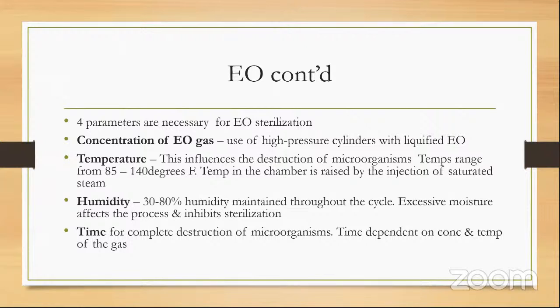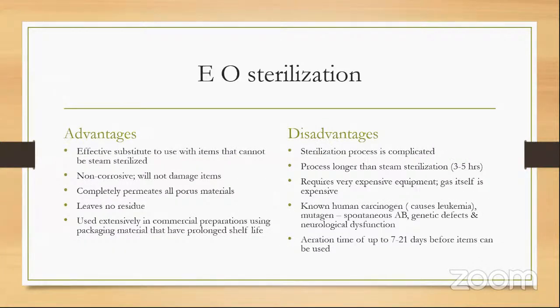So it's low temperature and there is some steam in it, because 30 to 80% humidity is needed for the efficiency of the cycle. But excessive moisture affects the process and inhibits sterilization. So it's just enough humidity, just enough heat, and just enough time for complete destruction of the microorganisms. The time for sterilization is dependent on the concentration of the gas and the temperature of the gas. But ethylene oxide sterilization can take anywhere between 3 to 5 hours. So it's a pretty long process.